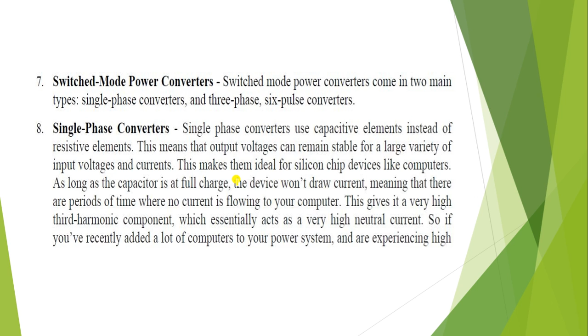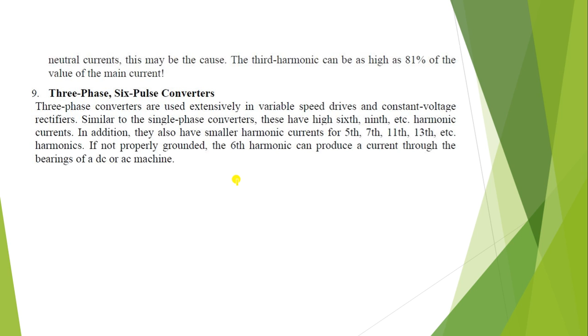Three phase, six pulse converter. Three phase converters are used extensively in variable speed drives and constant voltage rectifiers. Similar to the single phase converters, these have high 6th, 9th, etc. harmonic currents. In addition, they also have smaller harmonic currents for the 5th, 7th, 11th, 13th, etc. harmonics. If not properly grounded, the 6th harmonic can produce a current through the bearing of a DC or AC machine.